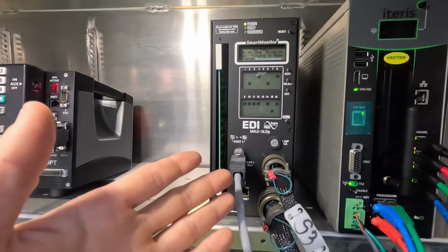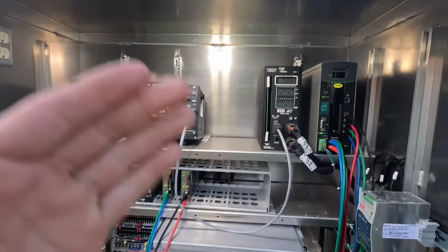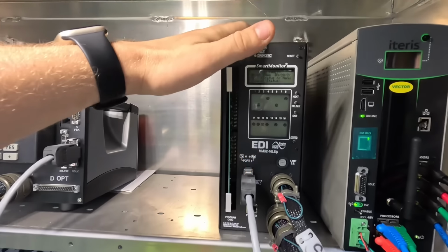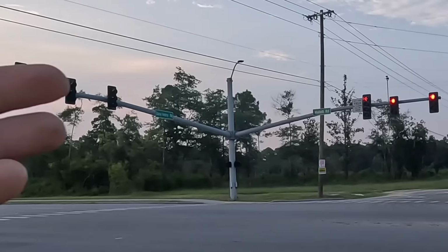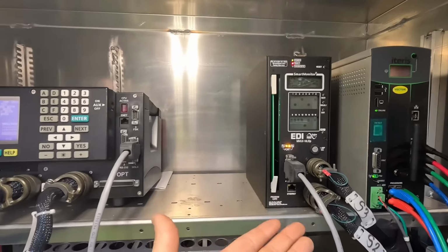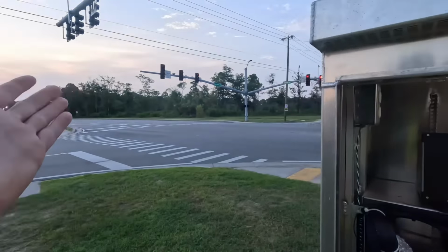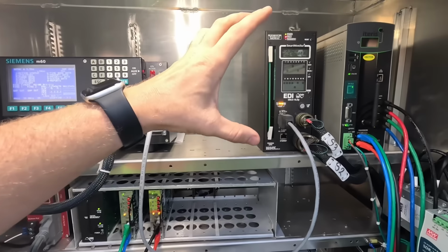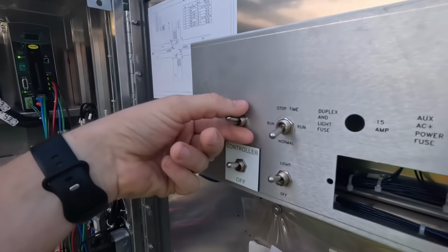And this MMU right here will monitor this controller and everything it outputs into the field at any given time. And if this has any kind of brain fart, this MMU will lock up the intersection and put it into flash, which will flip the switch here, and I'll show you an example. It's now flashing all red around this intersection. That's what this MMU is going to do if it sees any faults or failures on this controller or anything out in the field or anything internal inside of this signal controller cabinet. This is going to see that and lock up this intersection and make it go into flash. Let's take it back out of flash now.